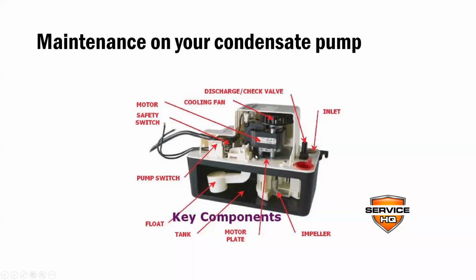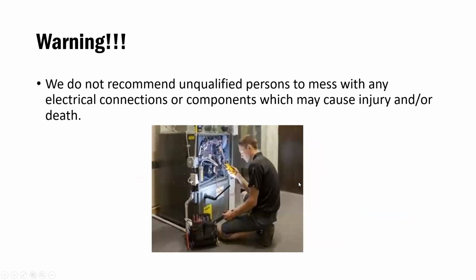But these condensate pumps, as you can see, there's a lot of working parts in them. And if you have one of those, it pumps your water out to the outside or over to your drain. Well, then we'll actually clean up the contents of that pump, because this black pan here is a reservoir that holds the water, and it can get nasty, and algae can start growing in there too. So we normally take those apart and just clean them.